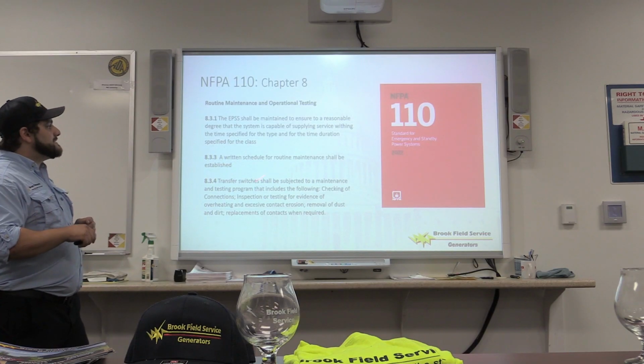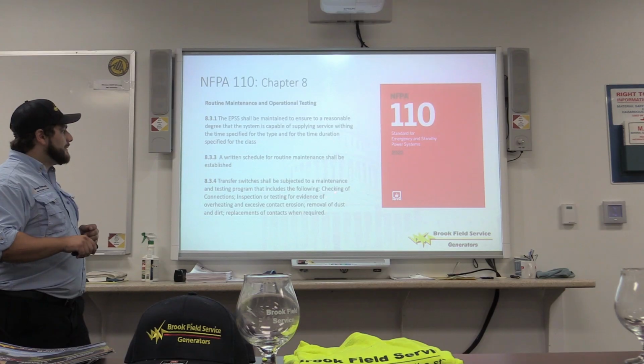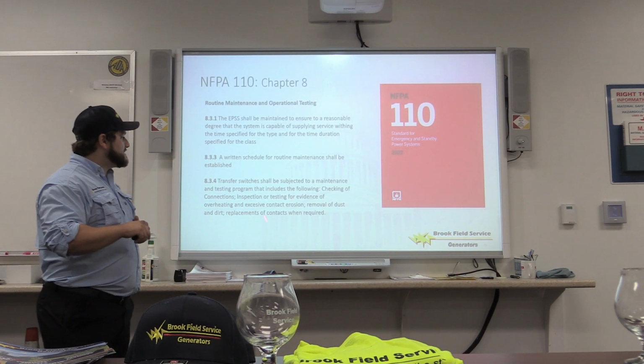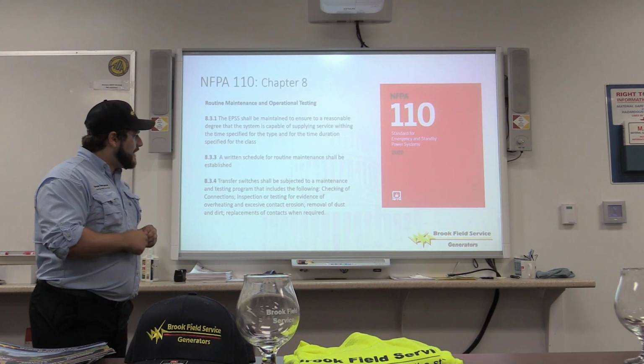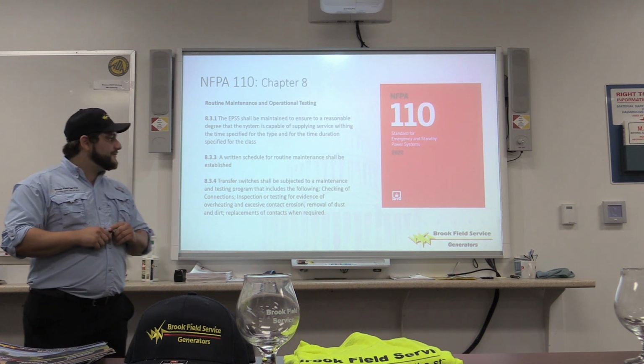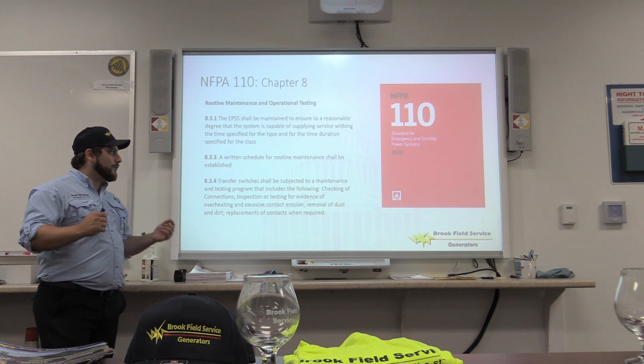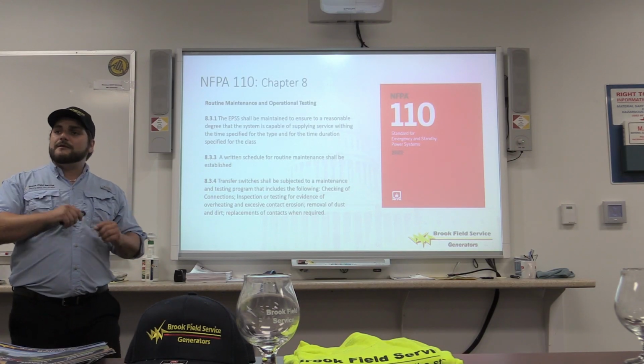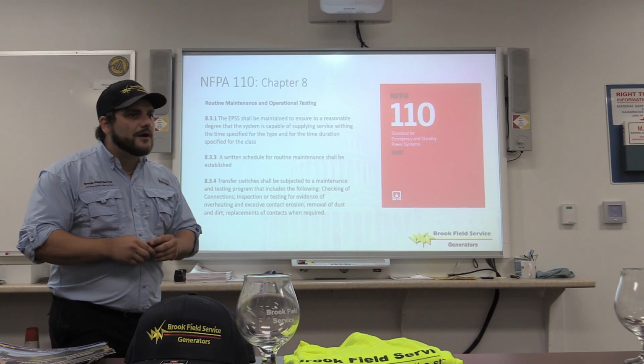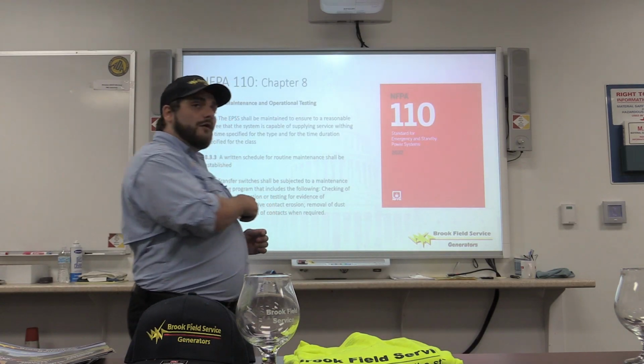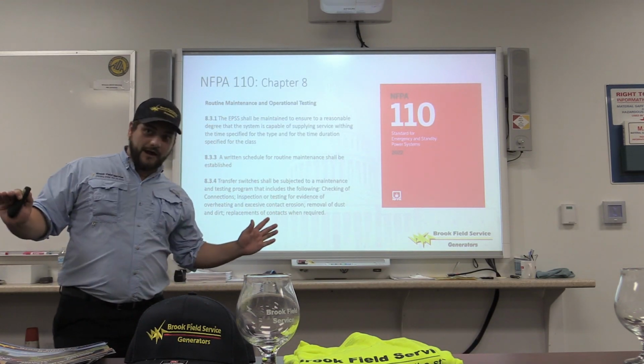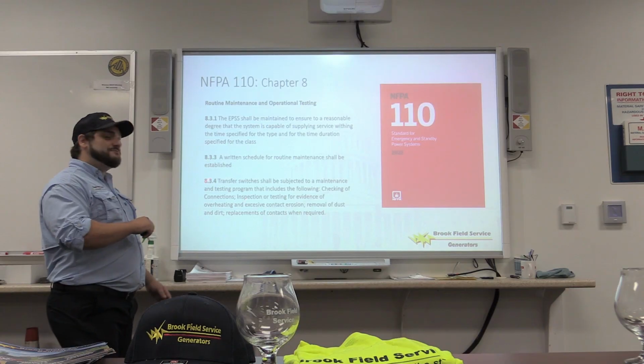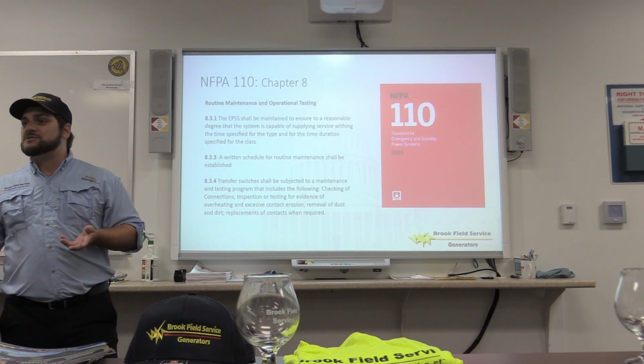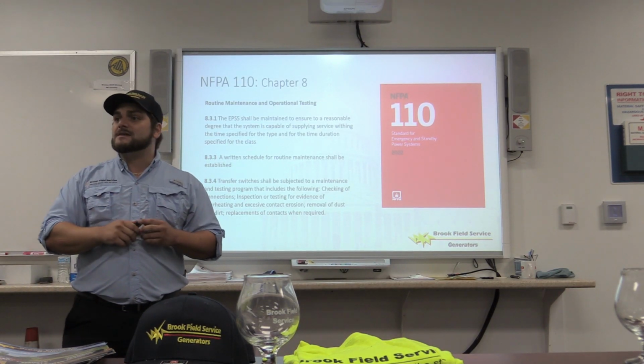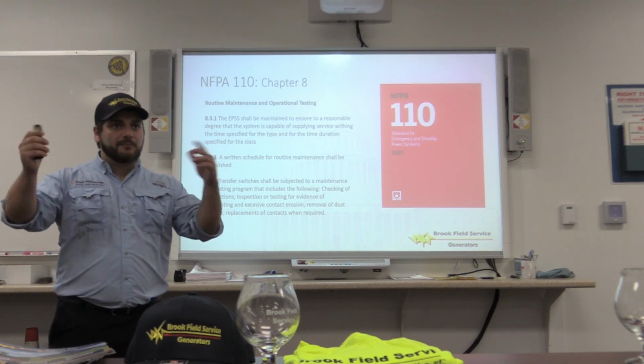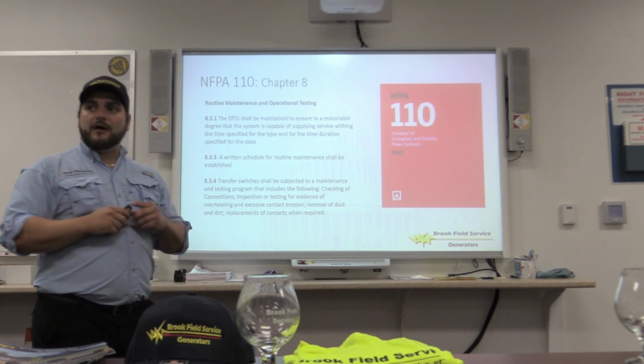And transfer switches shall be subjected to a maintenance and testing program that includes the following: checking of connections, inspection or testing for evidence of overheating and excessive contact erosion, removal of dust and dirt, as well as replacement of the contacts when required. And when I said earlier that there's a lot of times where guys tell me, oh, we do all ourselves, we test things ourselves. I don't know if you do it or not, good, God bless if you do, but you guys really aren't supposed to be doing any work on the transfer switch yourselves. That's when one of our certified techs come in, or you have to hire an electrician, whatever you prefer. But as we'll talk about, we do both.